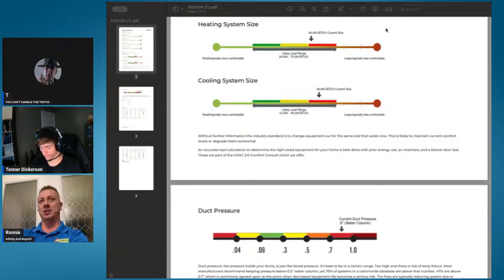The upstairs was an air conditioning only system. We put in a heat pump and an air handler, and it was supposed to have a heat pack in it, but not hooked up, in case the guy ever wanted it. Then install hooks up a 10 kW heat pack on a 12-2 wire at ground on a double 20. The guy kicks the heat on, the breaker trips. This house has never had heat upstairs - well, it's had heat, but off the main system.